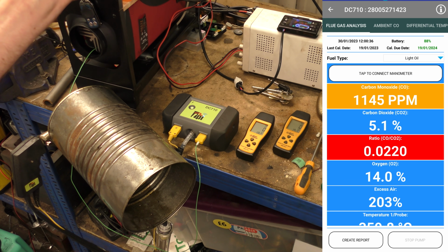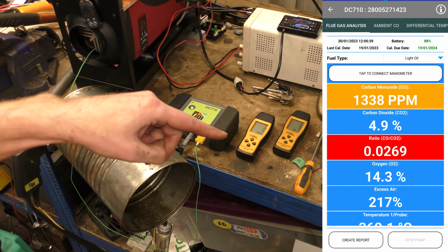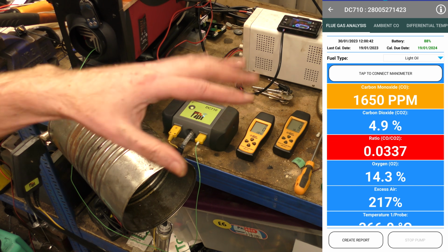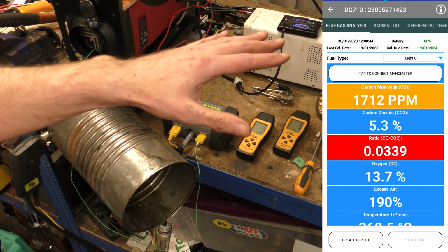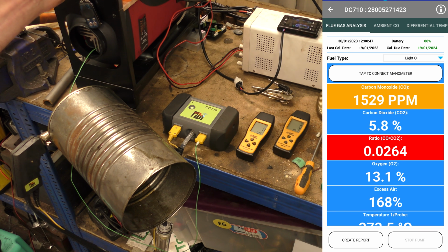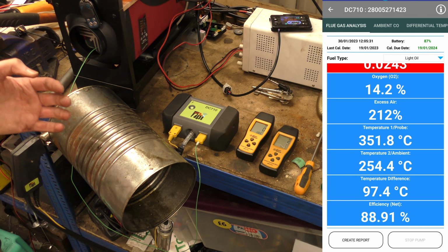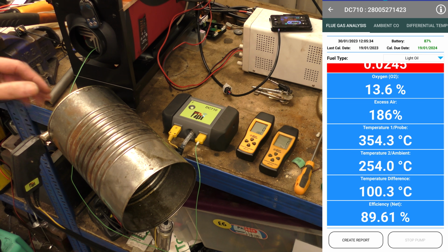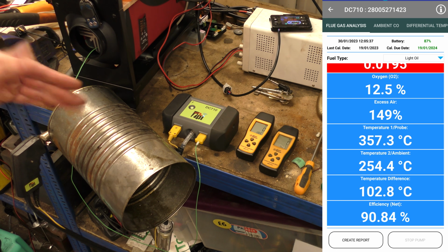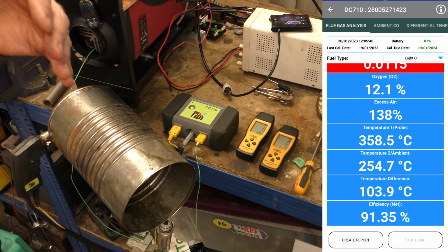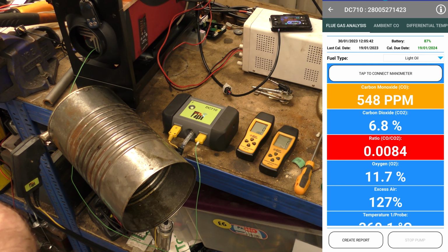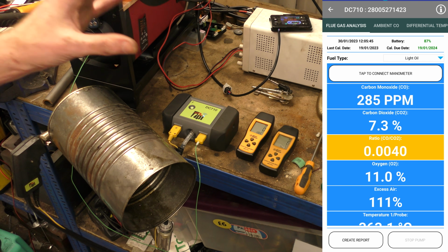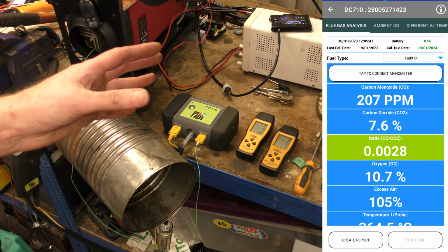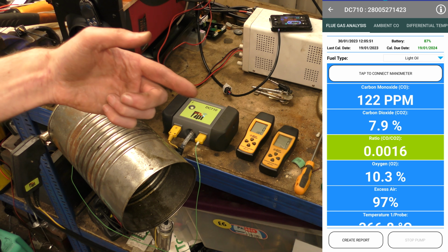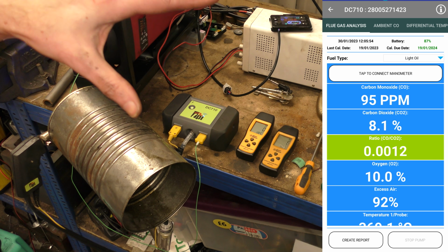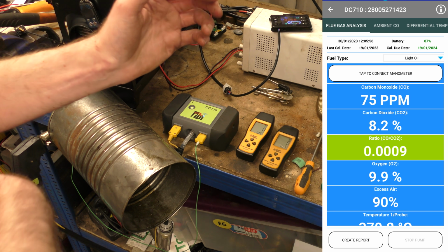So it's seen it's too hot and throttling back the fuel, it basically almost goes out. Wow, that's quite interesting. So from this we know our housing temperature is way too hot because it's clipping out, hitting max temperature, and then having to throttle the fuel pump back, which generates even more carbon monoxide, which generates soot. So we need to find the sweet spot of having the right fan speed and right fuel speed, keeping the housing temperature right so it doesn't throttle us back.